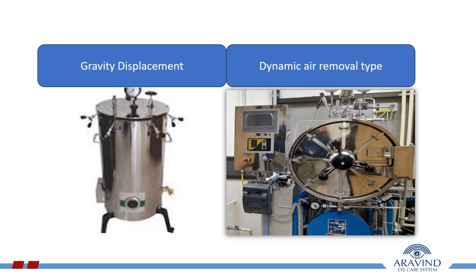In a vertical autoclave, we do not have any printing options, so we cannot monitor the sterilization cycle. As per NABH norms, pre-vacuum autoclave machines are suggested for good quality of sterilization.